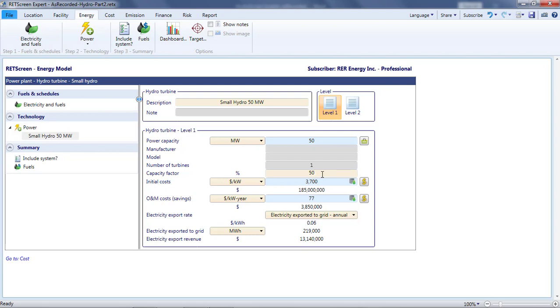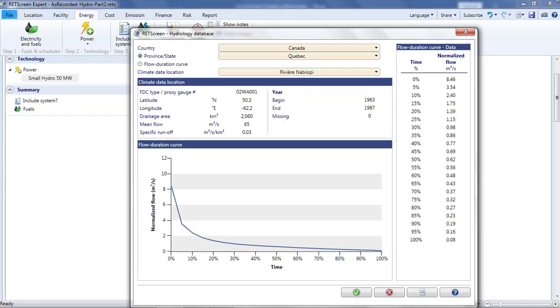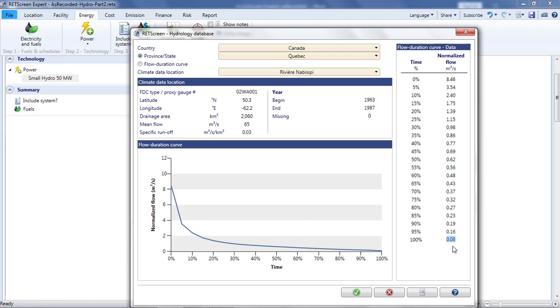I need to tell RETScreen the head, the mean flow on an annual basis, and information that describes how the flow varies around the mean over the course of the year. If I'm only interested in the annual production of electricity, I don't really care when the flow is strong and when it is weak. I just want to know, for any given flow rate, what fraction of an average year the available flow will match the given flow rate. In the hydro industry, this is often specified through a so-called flow duration curve. Here's an example of a flow duration curve. On the vertical axis, we have the volume flow rate, in cubic meters per second. The highest value attained by the curve is 8.5 cubic meters per second.